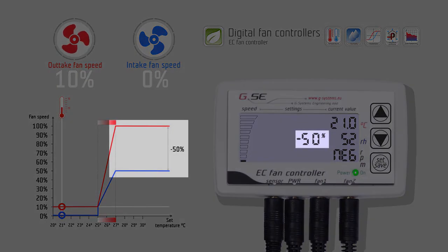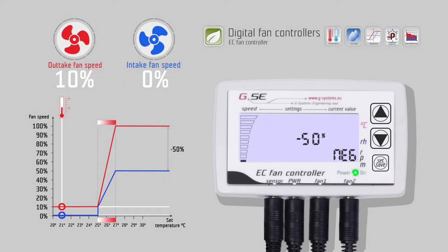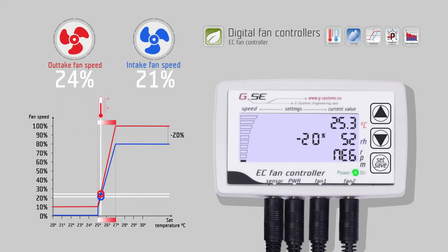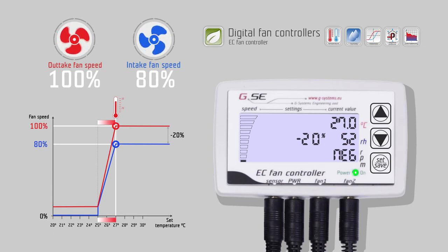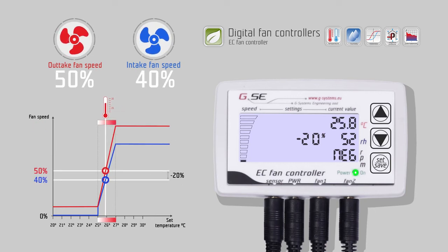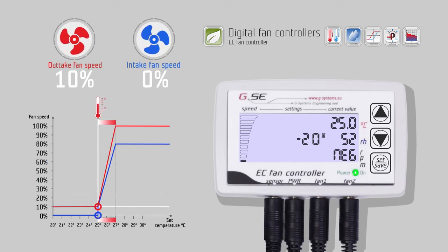The negative pressure decreases the speed of the intake fan. For example, we set the value to -20%. When the exhaust fan operates at full load 100%, the intake fan stays at 80%. If the exhaust fan runs at 50%, then the intake fan runs at 40%, -20% of its power. The exhaust fan removes more air from the room than the intake fan blows inside, and you obtain a guaranteed negative pressure during the regulation.